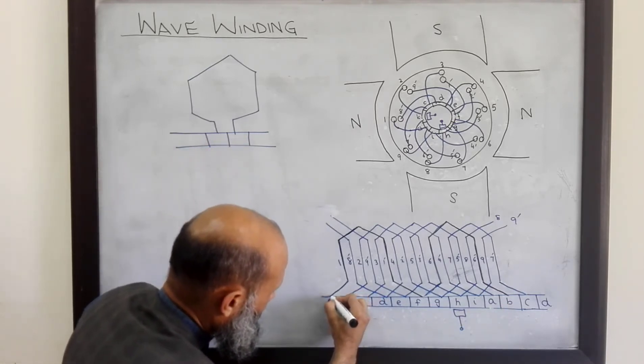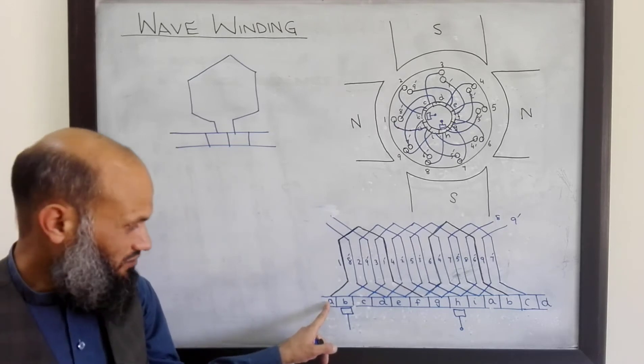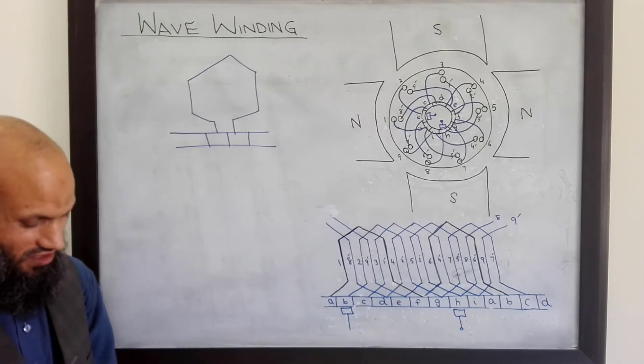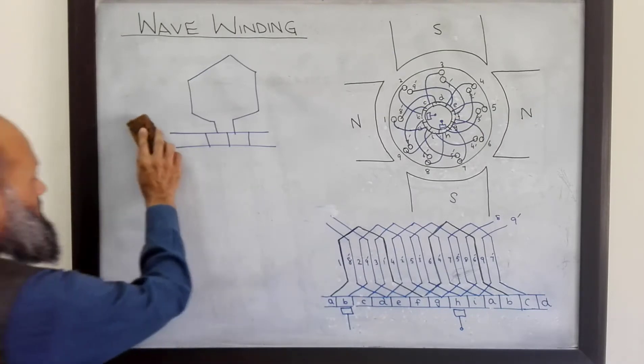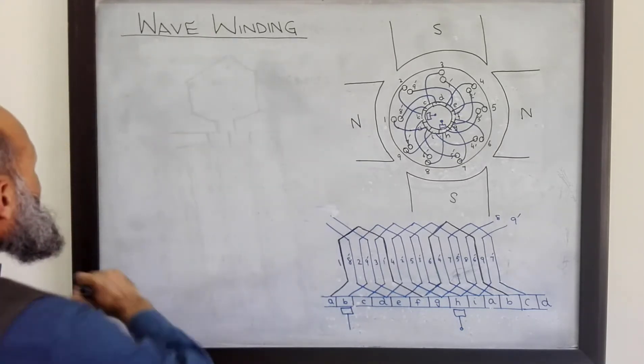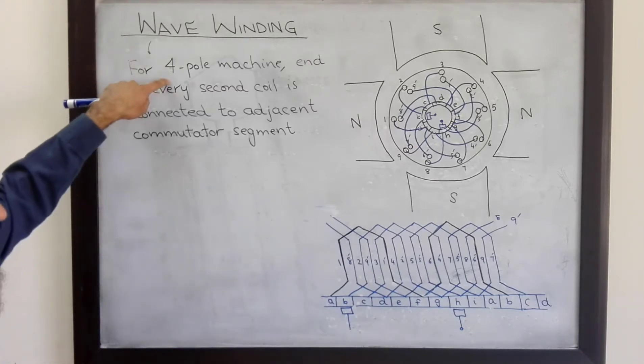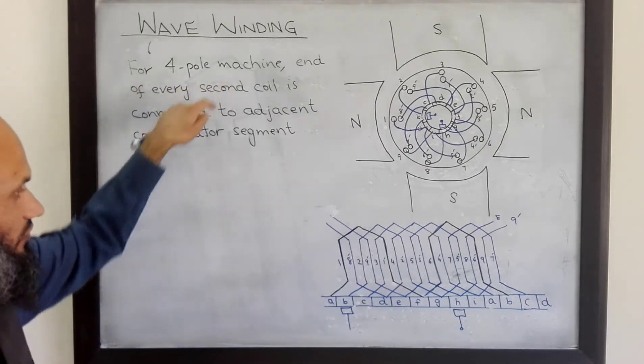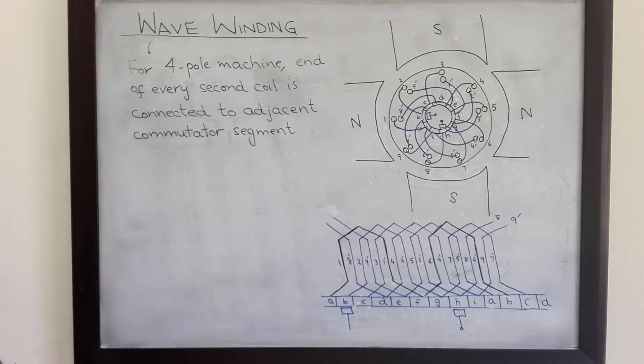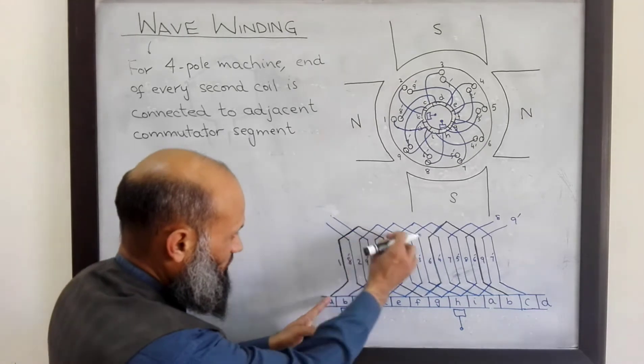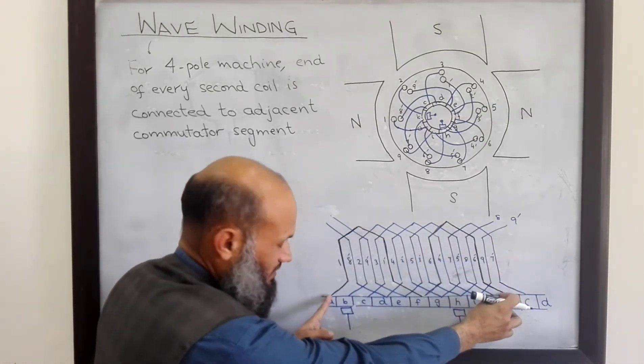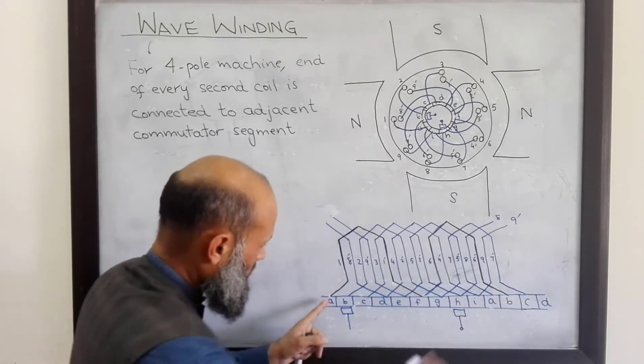This is connected to segment A. And the end of the second coil is connected to commutator segment B. So the arrangement in case of wave winding — in case of wave winding, for a four-pole machine — the end of every second coil is connected to the adjacent commutator segment. This is the first coil, and in series with it is the next coil, and the end of that coil is connected to commutator segment B.